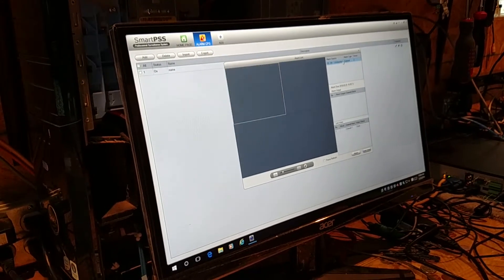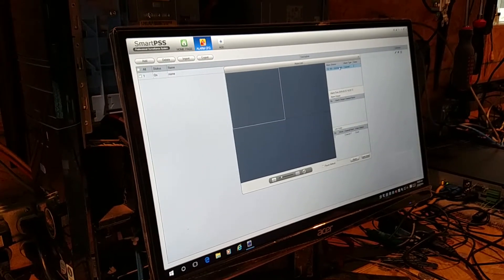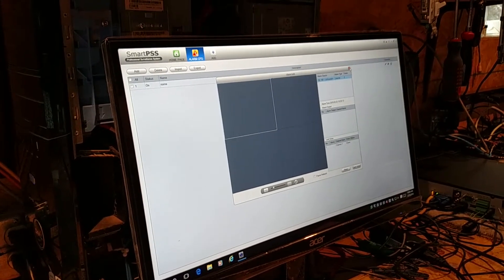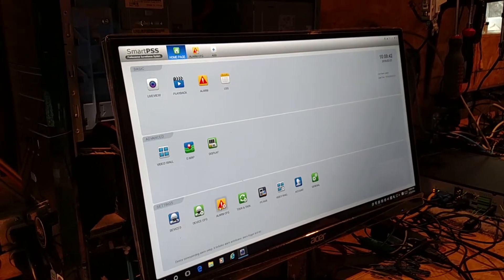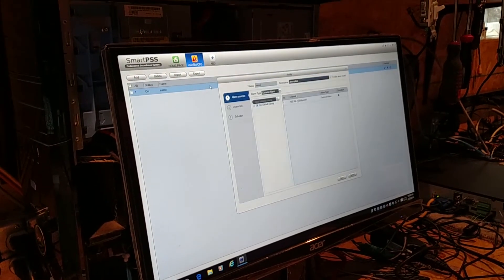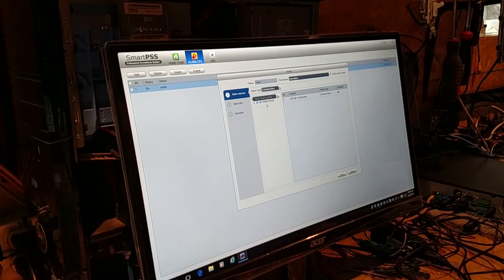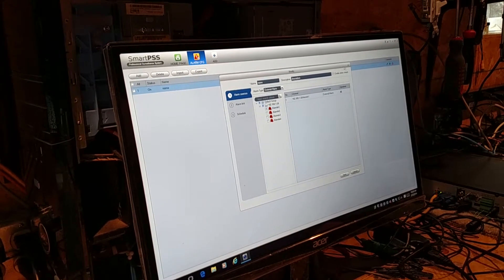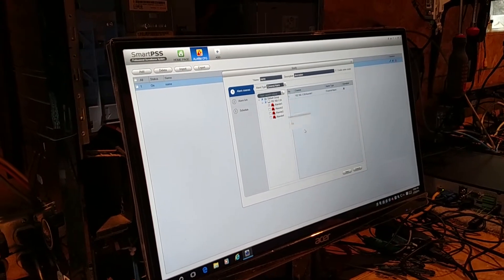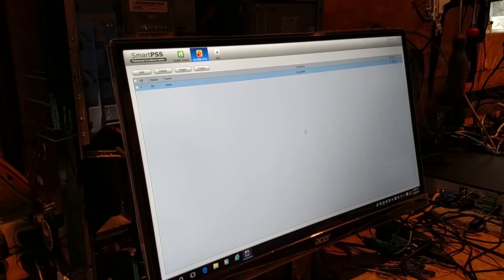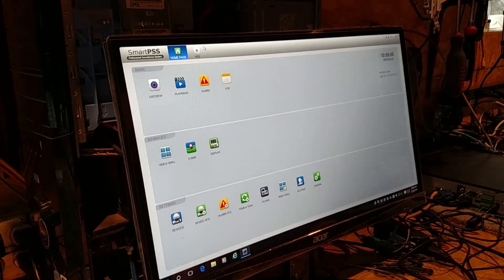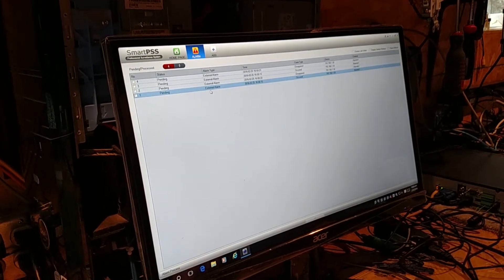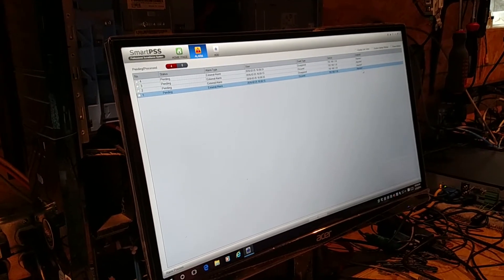That doesn't tell me a whole lot of anything. It would be nice instead of saying alarm in one if it showed me a name or a description, because I created this alarm here and there's a name and a description. I need more than just alarm in one to show up on there so that the operator of the computer knows what that alarm meant.